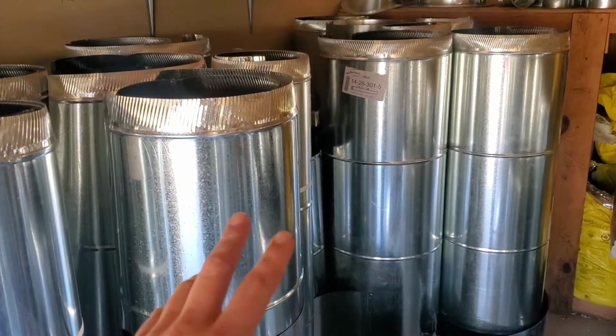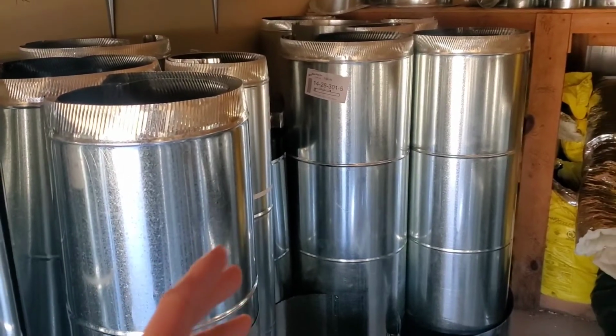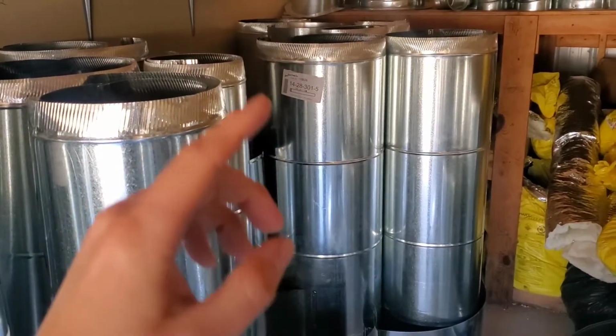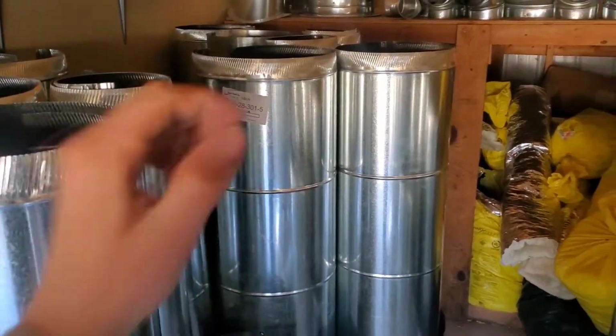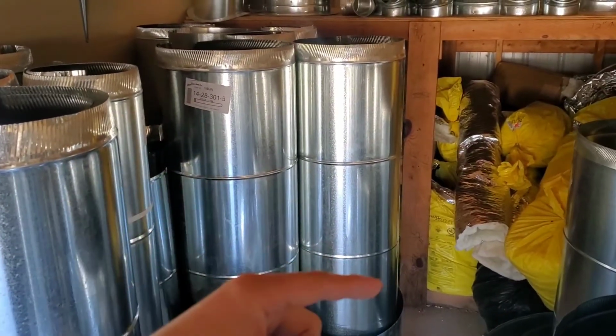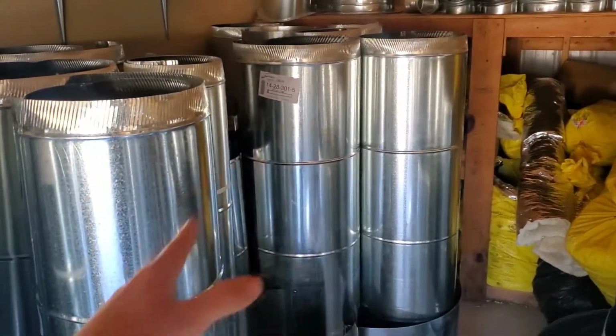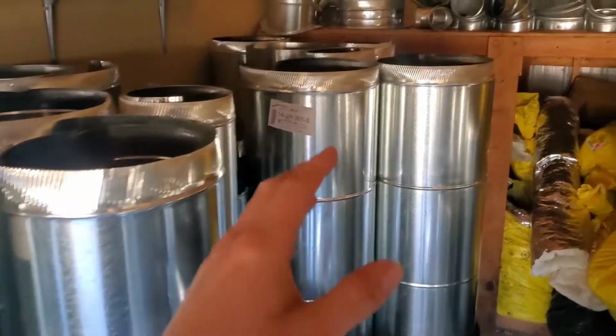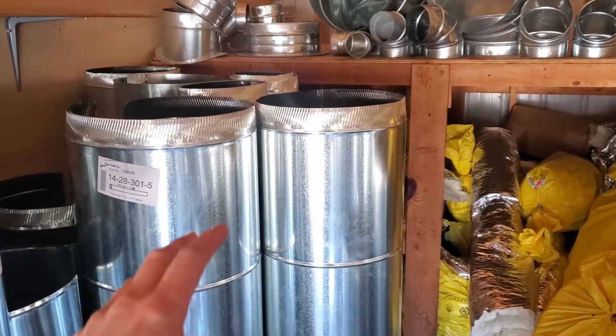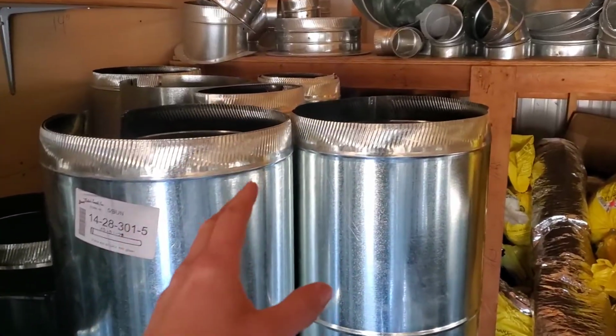This is standard. And if you're using rectangular, you should be using 1-inch liner instead of 1/2-inch. However, round duct, in my opinion, airflow velocities can be a little bit better. It's easier for the air to flow through the duct compared to the rectangular duct. But then again, I love rectangular ductwork just because you can custom build it to fit the job, and aesthetically it's more pleasing to the eye. But this is round duct.